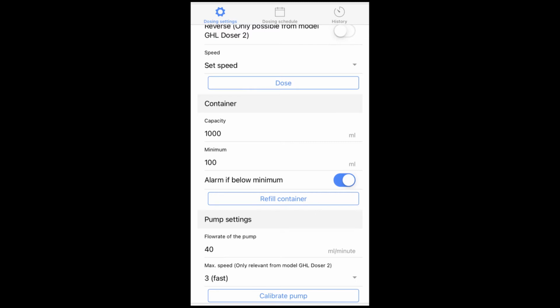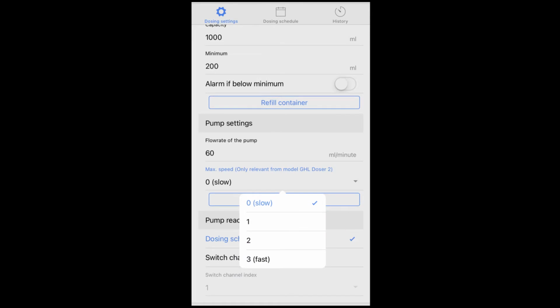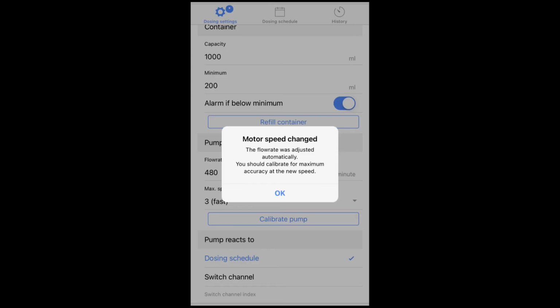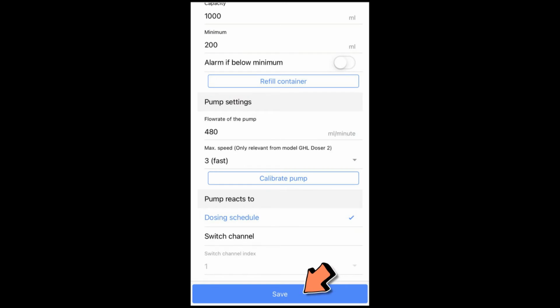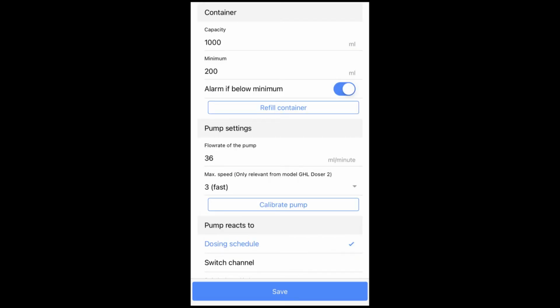Scroll down to the pump settings and change the max speed of the dosing pump from 0 to 3. A pop-up box will appear stating the motor speed is changed. Click OK and then choose the Save button. Calibrate the pump and when completed, enter in the flow rate of the pump, then click Save. With the reference A pump now configured, it's time to calibrate the reference B pump.